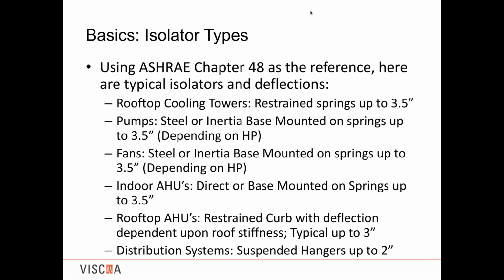the support structure. And as you go up higher in the building, this ASHRAE Chapter 48 will tell you you need more deflection because the building itself, as you get very tall, becomes a spring. And a lot of this equipment is also attached to diaphragms or slabs within the building as you go up in the building. If you're in a building with, say, 20-foot column spacing, the diaphragm itself will be a lot stiffer than if I had a 40-foot column spacing. At some point, this diaphragm, the concrete slab that the equipment is resting on, can become like a trampoline. So that has to be factored into the equation, which analytically most of the textbooks would ignore.